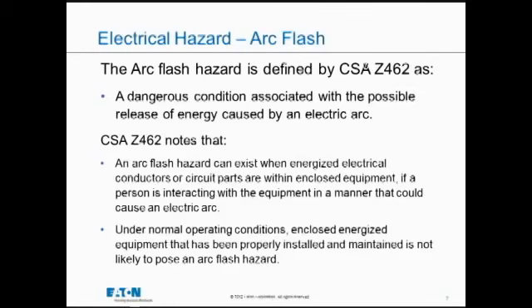In the 2008 standard, CSA Z462, there was a note attached to this definition that said that the arc flash hazard might be present if you're just interacting with the equipment. You're just opening a door or you're just turning something on or off. Possibly that arc flash could exist. And that caused a lot of, let's say, discussion with regards to whether it does or does not exist. And there is no easy button, there is no black and white answer.